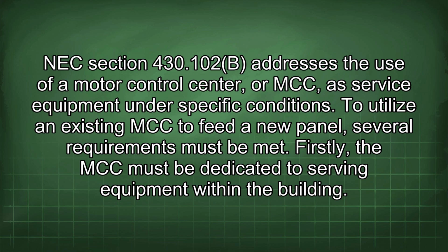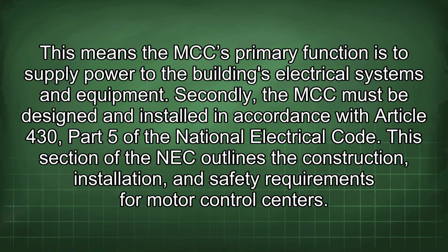To utilize an existing MCC to feed a new panel, several requirements must be met. Firstly, the MCC must be dedicated to serving equipment within the building. This means the MCC's primary function is to supply power to the building's electrical systems and equipment.